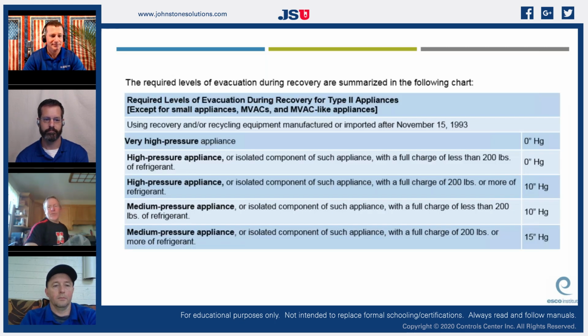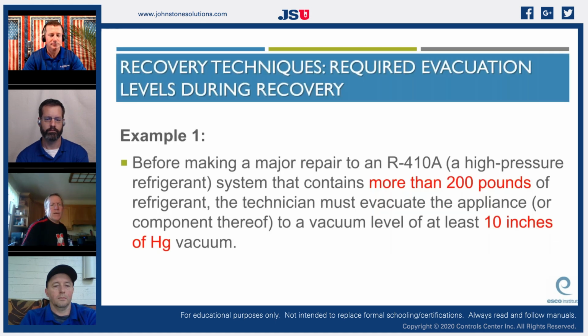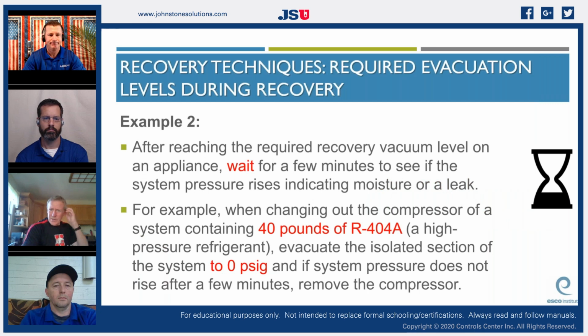This is another one of those charts where people are always going, hold on, I've got to write all this down. No, you don't have to write all this stuff down. Very high pressure and high pressure appliance for less than 200 pounds, 0 inches mercury evacuation. High pressure appliance over 200 pounds, 10 inches. Medium pressure, less than 200 pounds, 10 inches. And medium pressure appliance over 200 pounds is 15. And this is basically an example: more than 200 pounds of 410 must be evacuated to a level of 10 inches mercury.